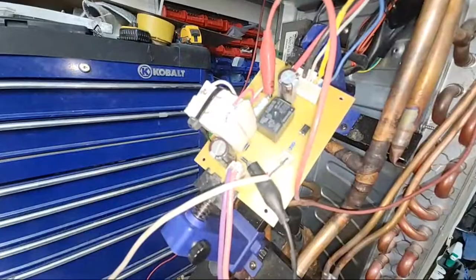So let's flip the switch and listen to the relay. That was about a half a second delay. That's good — that's half a second where the capacitor charged up with the current limiting resistor, 470 ohms I think. Once it got to be enough voltage, think of drop-in, drop-out, like a potential relay for a start capacitor — it's kind of the same thing. It has to get up to a pretty high voltage before it pulls in the coil, but then the voltage has to drop down quite a bit before it lets go.